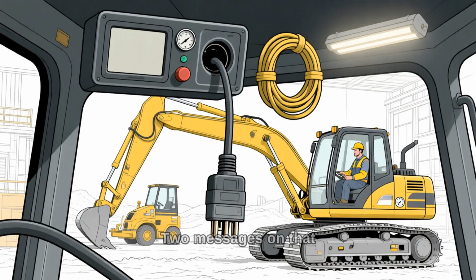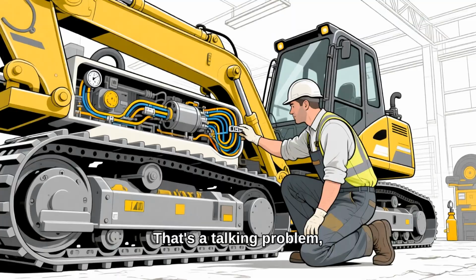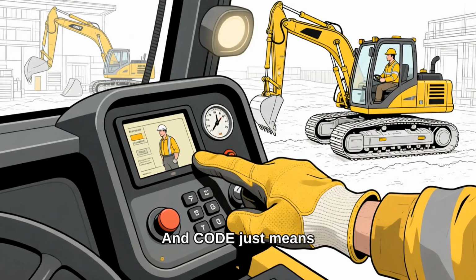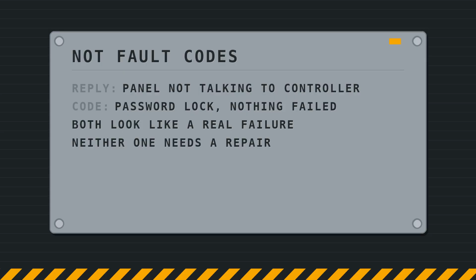2 messages on that screen aren't faults at all. REPLY means an instrument panel isn't communicating with the controller. That's a talking problem, not a broken solenoid. Chasing the circuit it mentions burns an afternoon for nothing. And CODE just means the controller is asking for a password. Nothing's failed. You're locked out. Knowing those 2 saves you a whole morning, because both look like a failure, and neither one is.